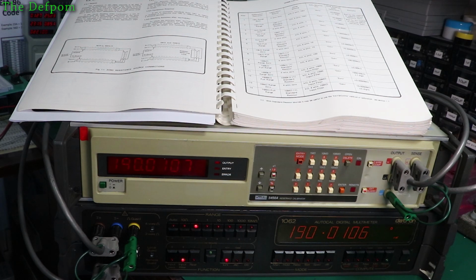Interesting. So maybe I can actually adjust the calibration by using the top end of the range. Right, let's try doing 100. What do we get? That's out by about 6 counts, 7 counts, 8 counts. So that's an acceptable trade-off. If I do 10 ohms, that's not out by much. It's only about 6 counts out. So I think that's probably a fair trade-off. If I calibrate the top end of the range instead of the middle, it gives the whole range a better accuracy. So that's an interesting little thing to find, isn't it? I didn't think it would actually do that. I didn't think it would handle it. It may still not. Don't know. It may cause an error.